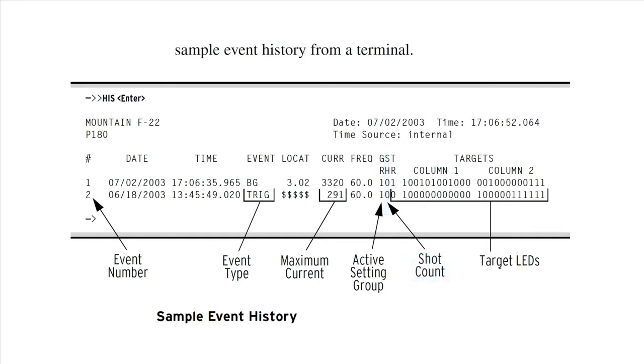This is an example of the event history from the 651R when downloaded. Looking at Event 1, you can see that it was a BG event at a distance of 3.02 miles. For the second event, you can see that it was a manual trigger, so no distance is recorded, and the current was less than the fault trigger setting. You can also see the active group setting and other pertinent data.